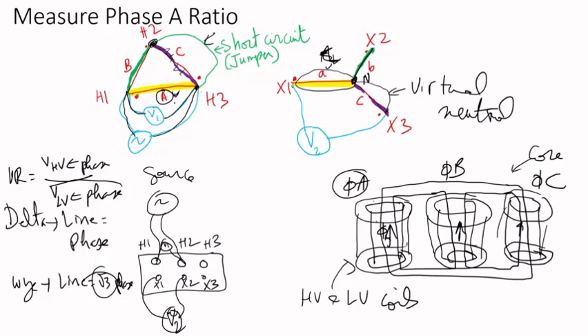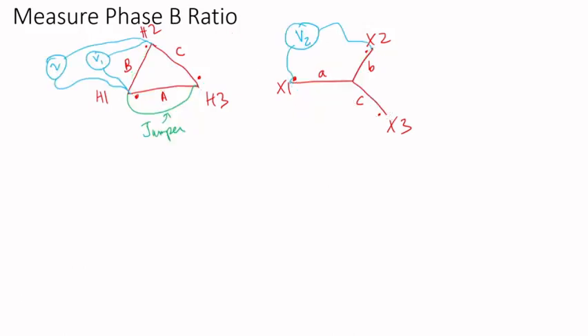Now I can measure from X1 to X3, but keep in mind this phase is shorted. So it's as if I'm measuring from X1 to this neutral point. I'm measuring phase to neutral. By shorting this phase, I created a virtual neutral. Then I don't have to worry about phase to neutral, line to line, or converting back to line to neutral. So this is for phase A.